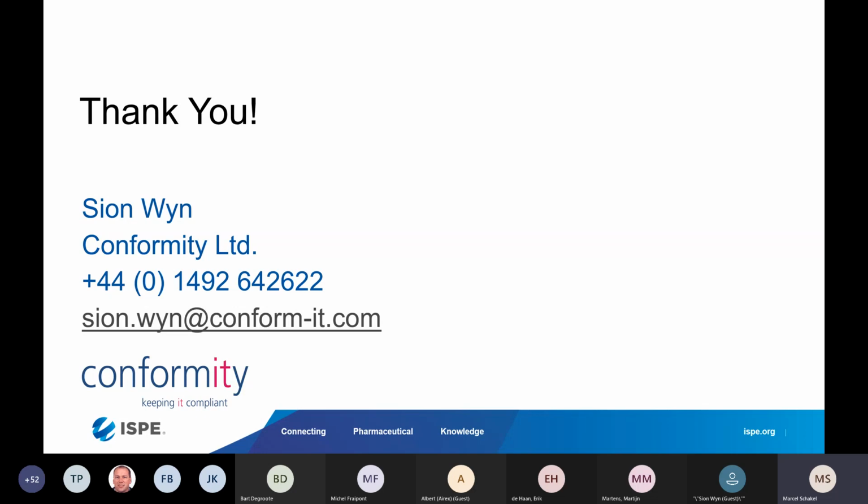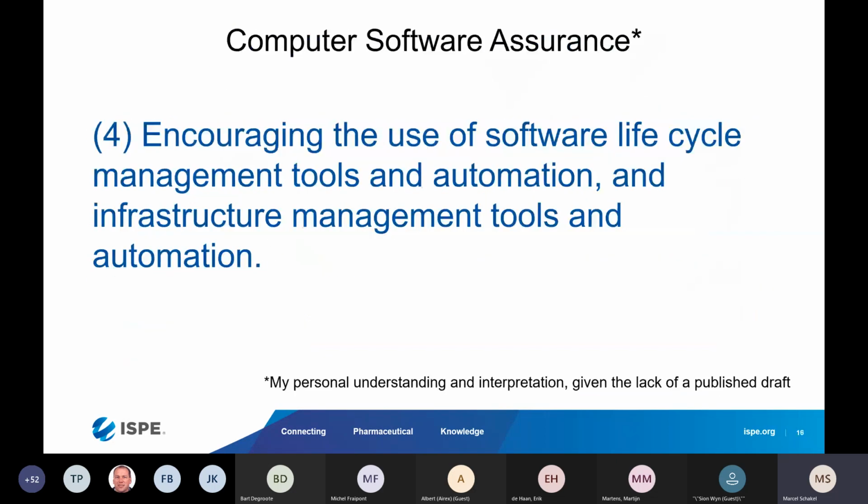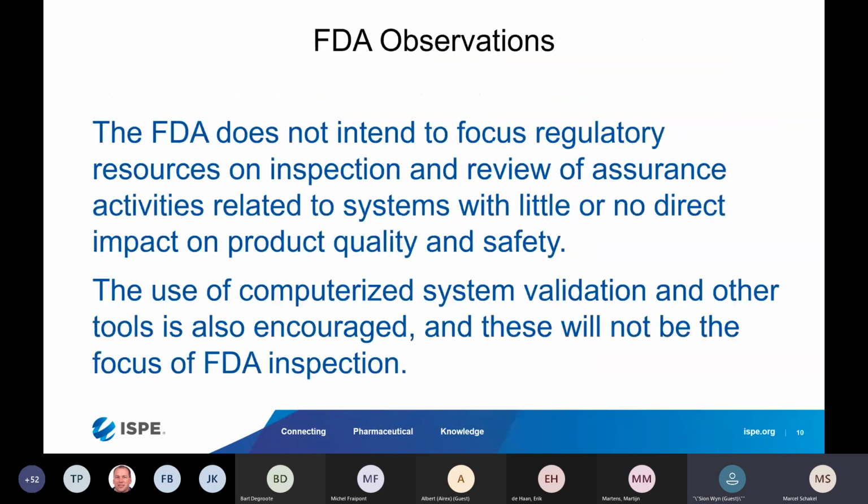We do have some questions for you, so I will mention. It was regarding slide number 10. The FDA has no focus on tooling. This means the tool still needs to be qualified or validated, or is an informal statement like "tool is properly tested" sufficient?